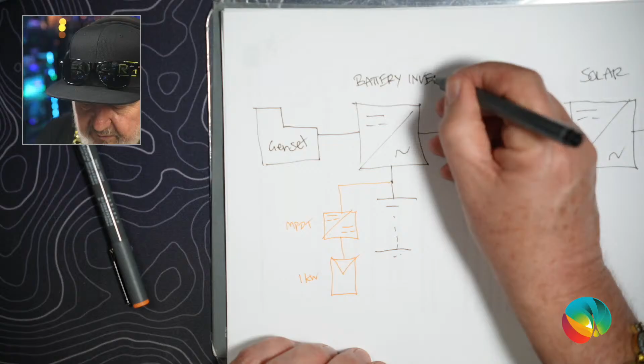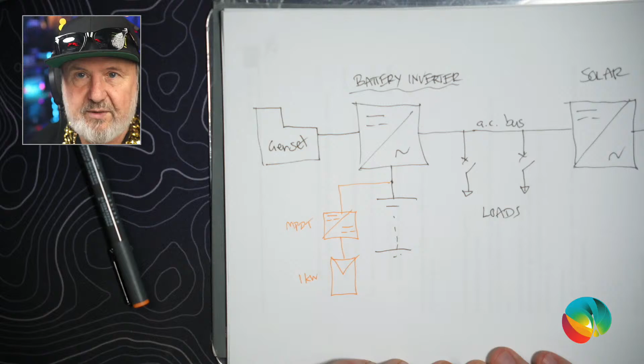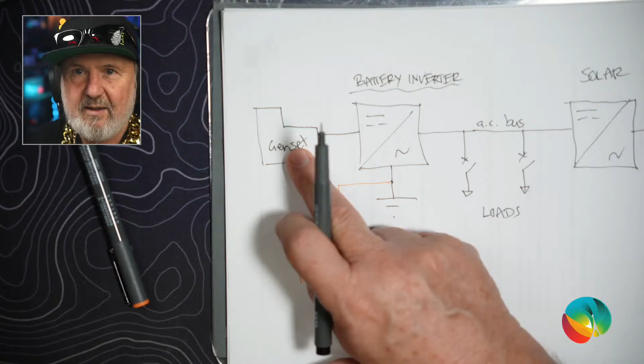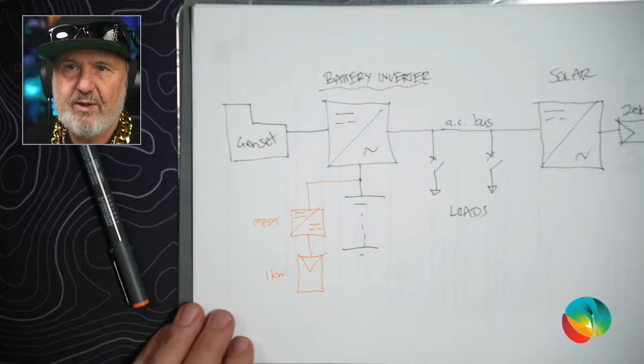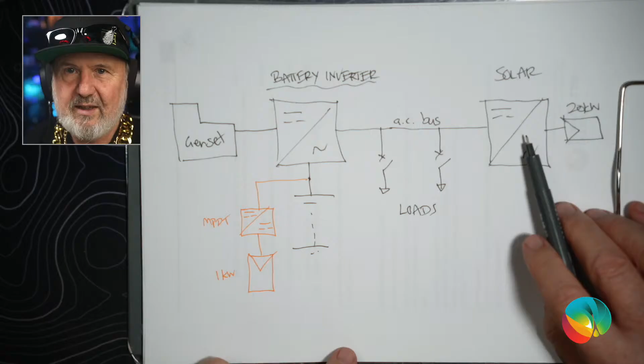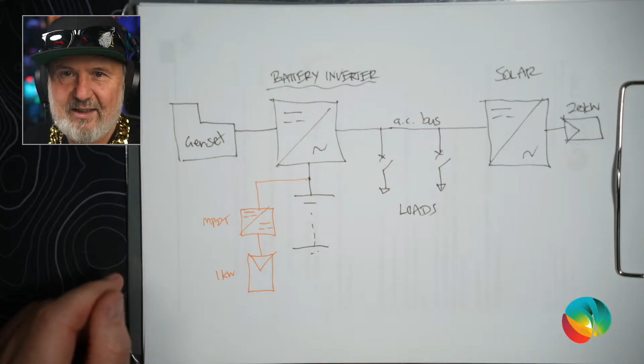Now, if for any reason it shuts down, like if our battery inverter shuts down because it's nighttime and there's low battery status and the generator didn't start, when the sun comes up in the morning, the solar inverter won't work. Your solar inverter is going to be waiting. The solar inverter is waiting for a grid to synchronize with, and the grid forming inverter is shut down. So you've got a situation where you've got sun, but you've got no charge.